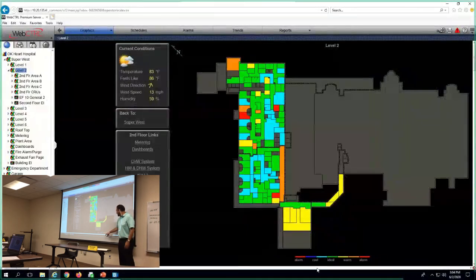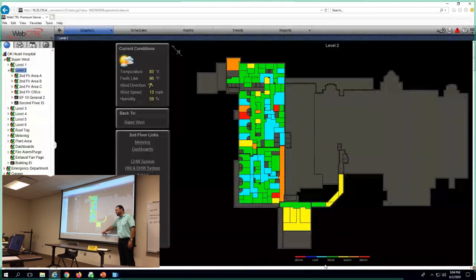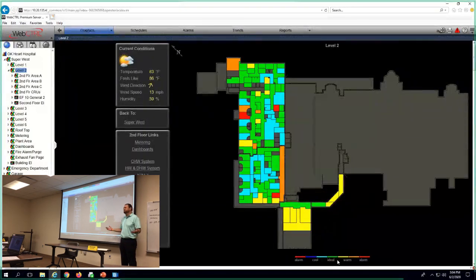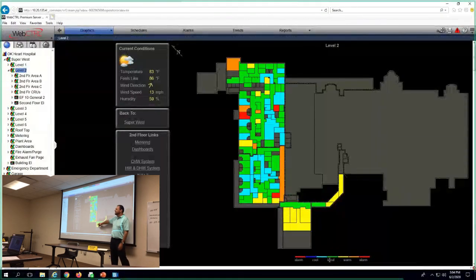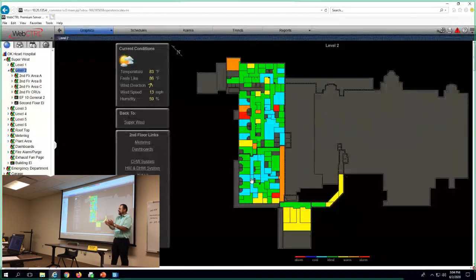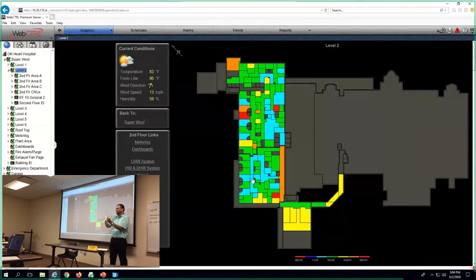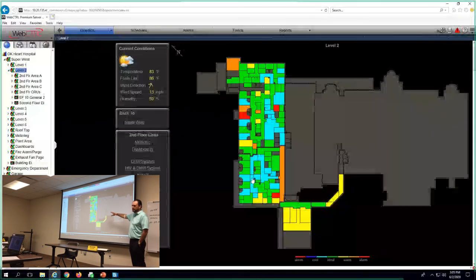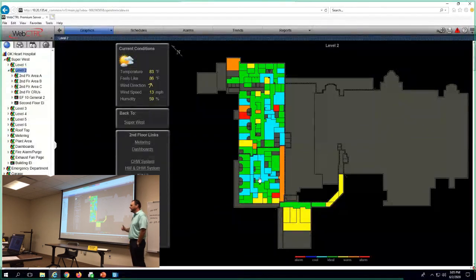So in this color bar, green is ideal, yellow is just slightly warmer than the cooling set point, light blue is slightly cooler than the heating set point. Light blues, yellows, and greens are okay. I can tell the conditions of the space by looking at those colors. Each one of these spaces right here is slightly above the cooling set point. Each one of these light blue spaces is slightly below the heating set point. I don't know what the heating and cooling set point is, but it doesn't matter as long as it's adjusted to where we allowed them to adjust it, and I can diagnose what's going on. So real quickly we can do that. A lot of times there's confusion about what the colors mean, and that's the goal, so you can quickly diagnose what's going on in the building. Anybody have any questions? We're going to get in a little more depth when we get into the spaces.